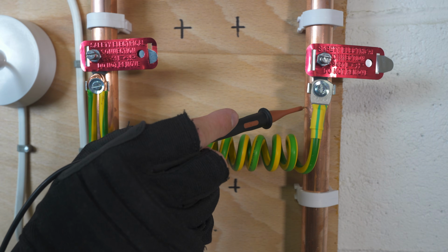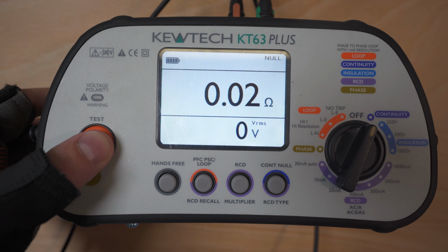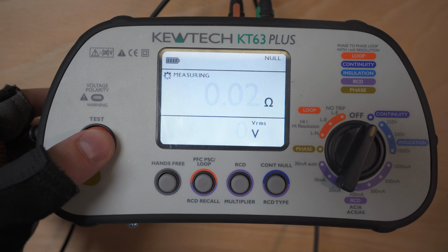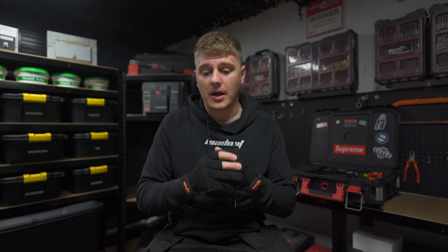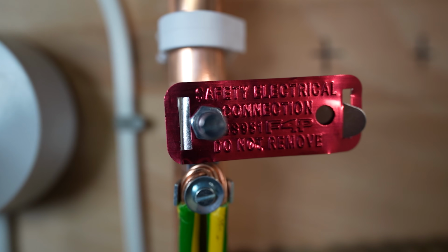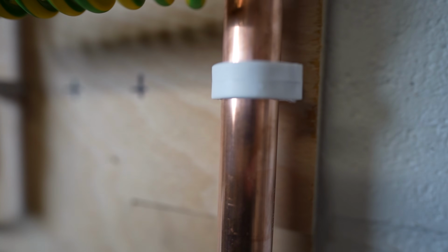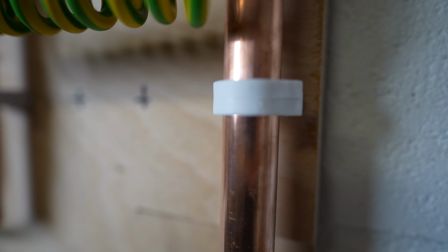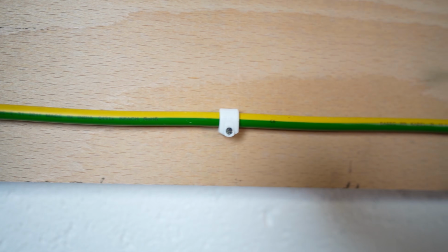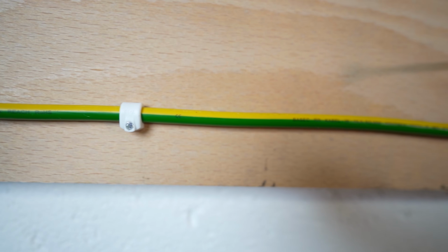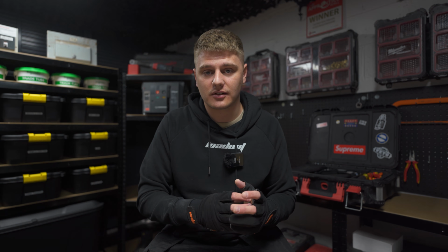Now, once complete, you actually want to put the probe on the extraneous conductive part itself and test again, and hopefully get a similar result to the one you just got. The first test tests for continuity and resistance of the conductor itself between the termination and the other end. But the second test actually proves that you've got a sound connection between the termination, whether that's a bonding clamp or a bolt or whatever, and the extraneous conductive part. It's all well and good having a nice low resistance piece of cable from the origin to the termination, but if it hasn't got a sound connection to the extraneous conductive part, then it's no good.